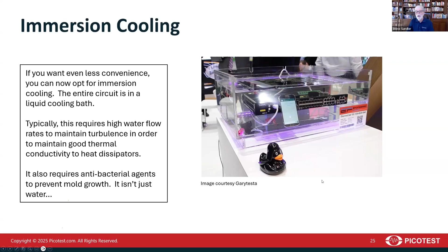Of course, there's not really water in there, because if it was water it would be growing algae, mold, and bacteria. So these are antibacterial liquids designed for cooling. Whether you're adding cooling manifolds or doing immersion cooling, however you're doing it, it adds a new layer of complexity between us and the ability to make measurements. And unfortunately, these cooling systems block most of our access anyway. There's very little here that we can actually connect to.